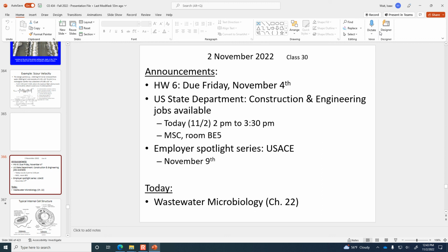One of the other parameters it mentioned that we can control is the dissolved oxygen. The dissolved oxygen is added to the aeration basin through fans and blowers, and it's very expensive to provide oxygen to the microorganisms, so you want to be sparing and judicious in the amount of electricity used. You want to provide just enough to support the bacteria so that they're removing the BOD quickly, but every additional gram of dissolved oxygen provided costs money to get in there.